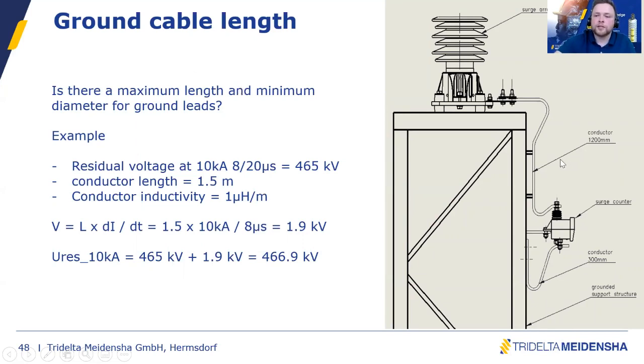So here on the right side, we see a typical installation of a porcelain housed surge arrestor. You have the insulation base, so the surge arrestor is galvanically separated from the steel support. Then we have the ground conductor, it's insulated and goes down to a surge counter, and the surge counter is grounded by a separate ground conductor. This ground conductor is 1.2 meters long and this one is 0.3 meters long. The steel structure is the boundary condition, it's completely grounded. So we assume that the complete conductor will be 1.5 meters.